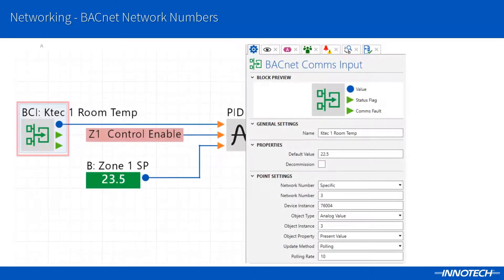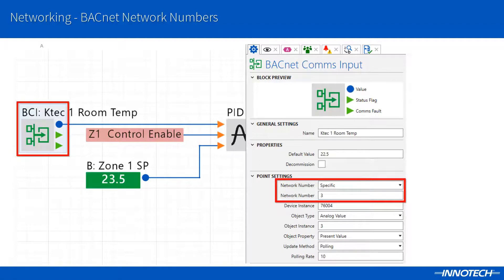During the design process, when using BACnet comms inputs or outputs, we recommend using the specific network number target. As shown in this example, I have set the BACnet comms input to read back the analog value from the BACnet MSTP device installed on network number 3. This helps to optimize and create an efficient BACnet network traffic flow. This can also be used for the BACnet comms output block to target a specific device and object on a specific network number.